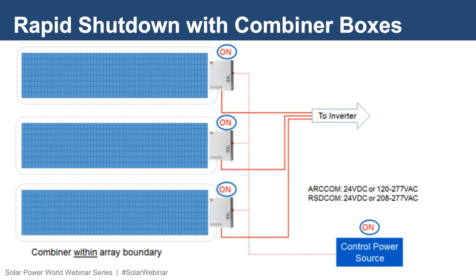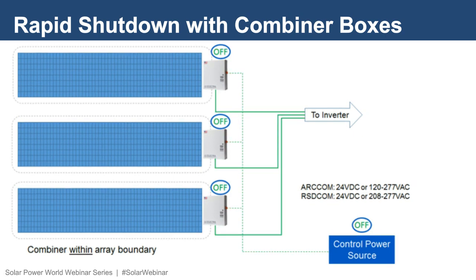When it's not possible or not feasible to install the inverters within the array boundary, you can utilize the Solectria RSDCOM combiner box product. In this case, you would install the combiner box within the array boundary, being 10 feet for NEC 2014 or 1 foot for NEC 2017. This combiner box now has the responsibility of isolating the PV output circuits, leaving the array and going to the inverter. In this example, the combiner boxes have a control power source present. When rapid shutdown is initiated, that control power source is deactivated. The contactors in the RSDCOMs open up, and the array is now isolated from the inverter.